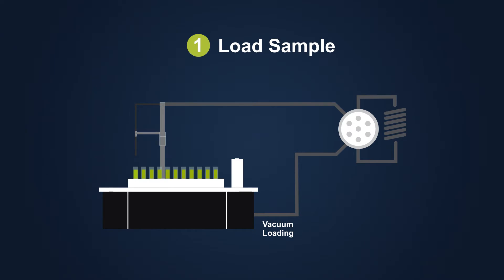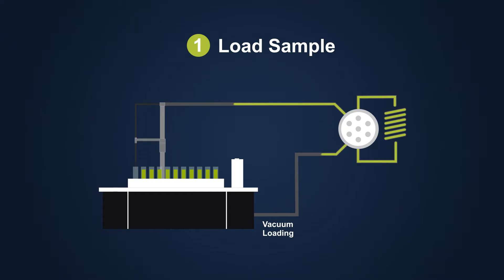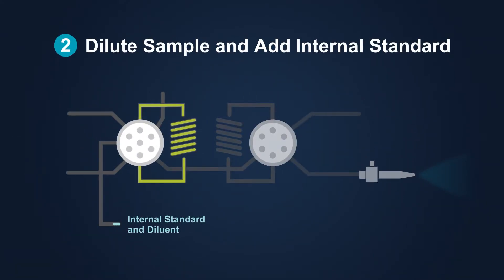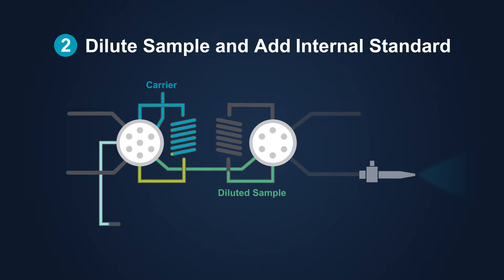During the analysis sequence, a precise volume of sample or standard is rapidly vacuum-loaded into a sample loop. Within seconds, the sample is automatically prepared by inline syringe addition of internal standard and diluent according to the dilution factor supplied from the ICP-MS software.